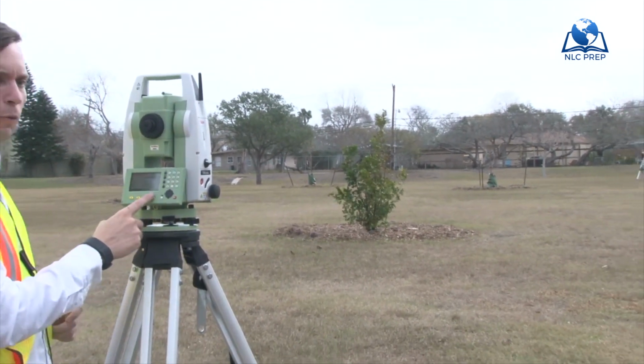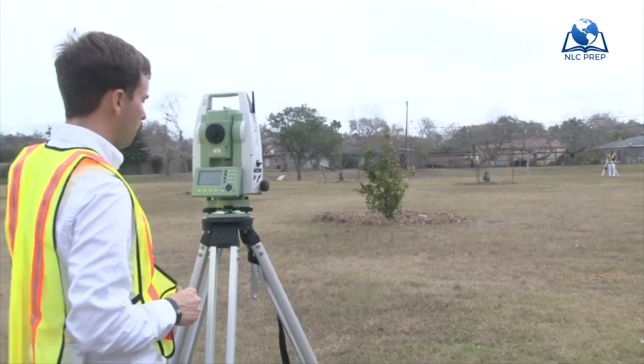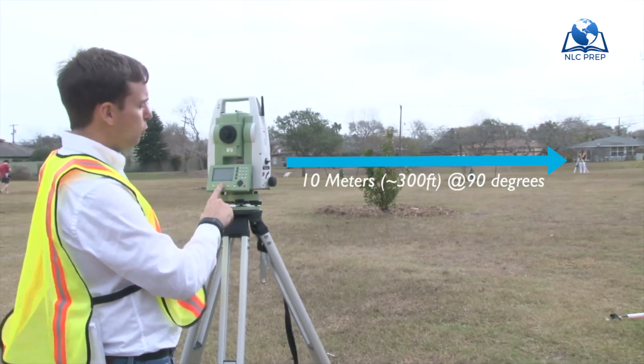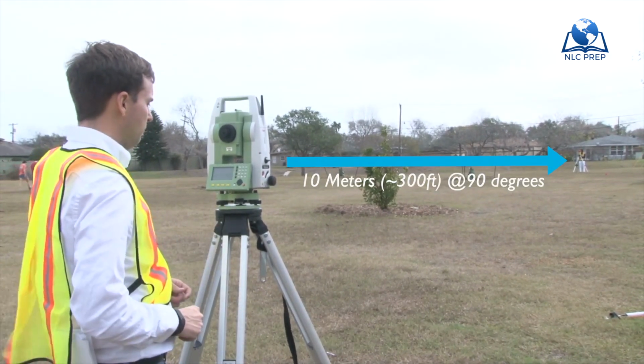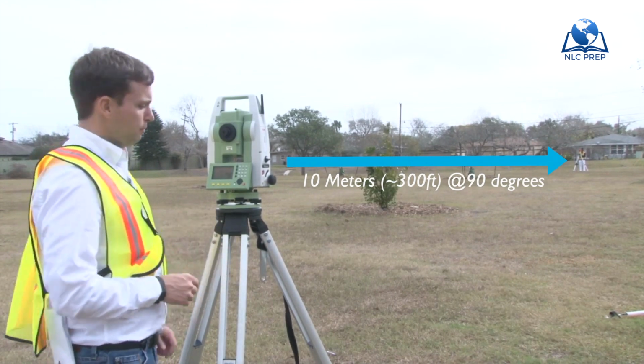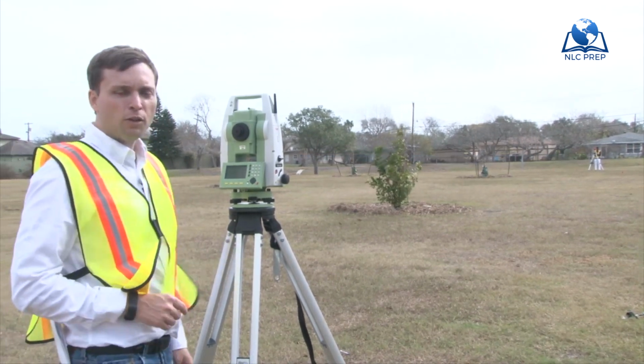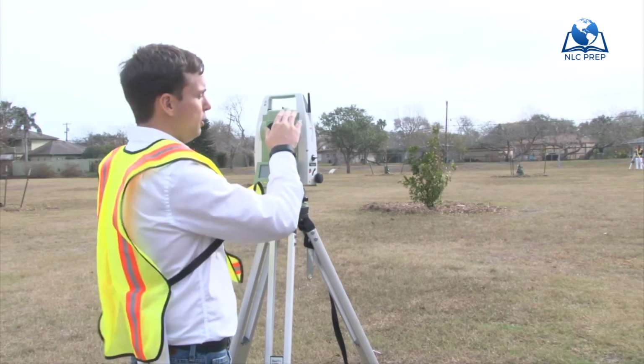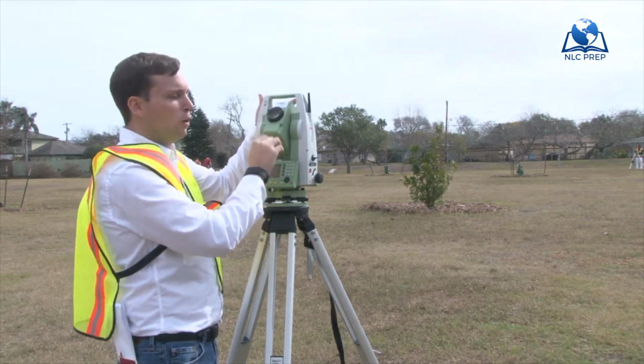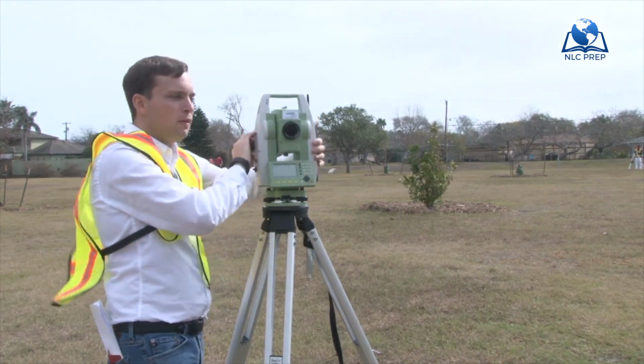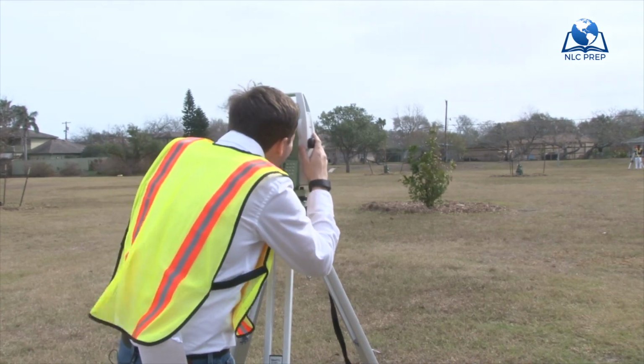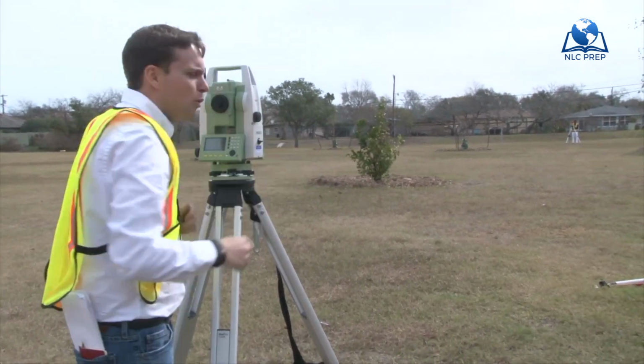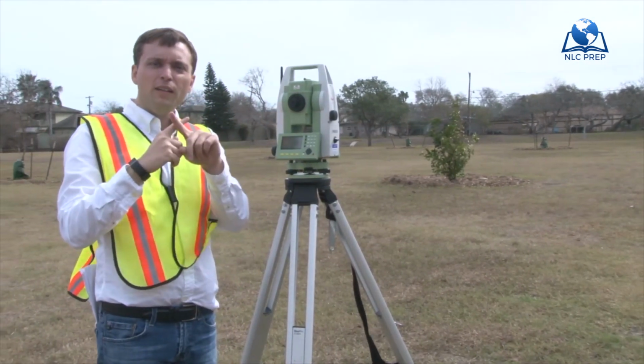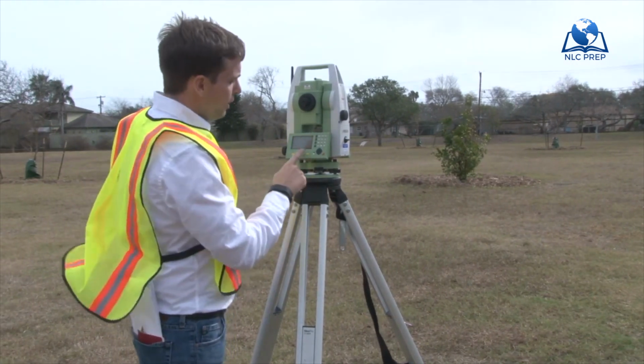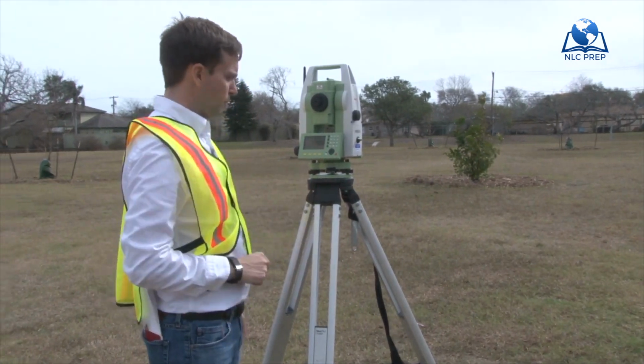After we've aimed, we'll hit Continue and then click Store. And it's going to take a measurement. Next, it's going to prompt us to change face. So we'll change from face 1 to face 2 and then turn the instrument. We'll line up directly in the center of that prism and hit Store.